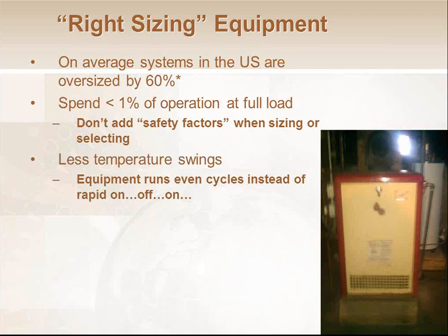The more correctly sized the boiler is, the less oversized it is, the fewer swings we're going to have in cycling the equipment on and off. If it's oversized, it's got to fire and then turn off, fire and turn off. We get a lot of comments from people saying, well, I'm going to buy a modulating boiler, so if I'm oversized, it'll just ramp down. Yeah, it's going to ramp down, but it only can ramp down so far. Depending on the boiler size and manufacturer, that may be 20%, maybe 30%, something like that. If I can only ramp down to 20% and it's a low load day, and my load is less than that, then I'm going to have to cycle on and off like I would have done with an old crappy boiler. So the modulating boiler does not save you in that regard.